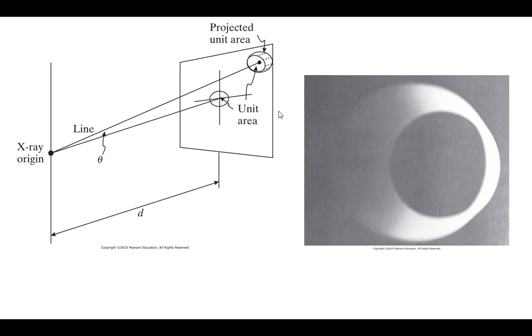That angle ratio is, again, cosine. So as you go further out, you got cosine squared due to the distance, and due to this oblique angle, you get another cosine. So that means it's going to be proportional to cosine cubed. So the actual intensity does not drop off on the detector plane as a square, it drops off as a cube of the cosine.